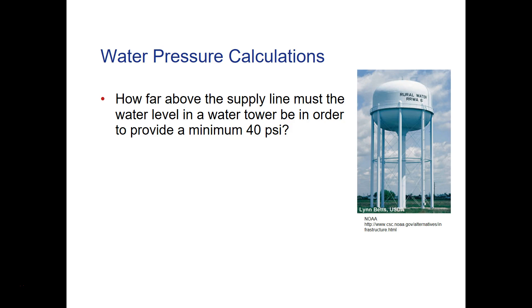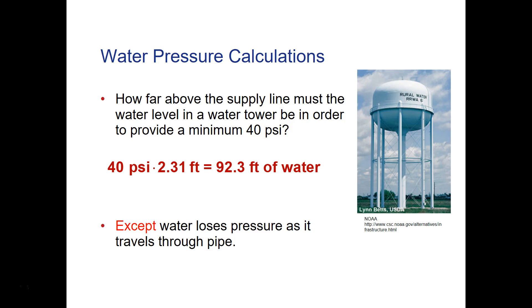So how far above the house must the water level be in a water tower to achieve the minimum 40 PSI pressure at a building? If you do that calculation: 40 PSI times 2.31 feet per PSI, we would need a distance of 92.3 feet of elevation to reach 40 PSI. However, there are water pressure losses as water travels through a pipe, so even more height may be needed.